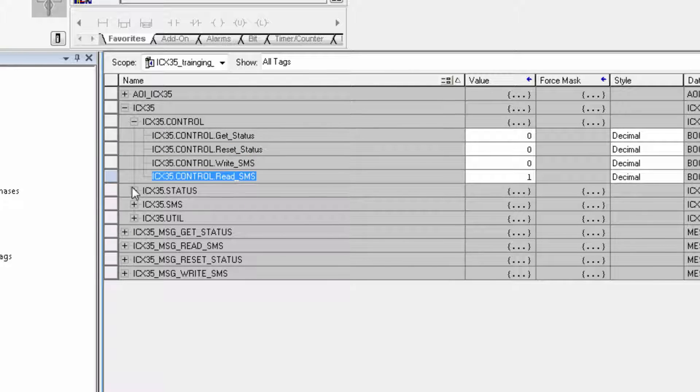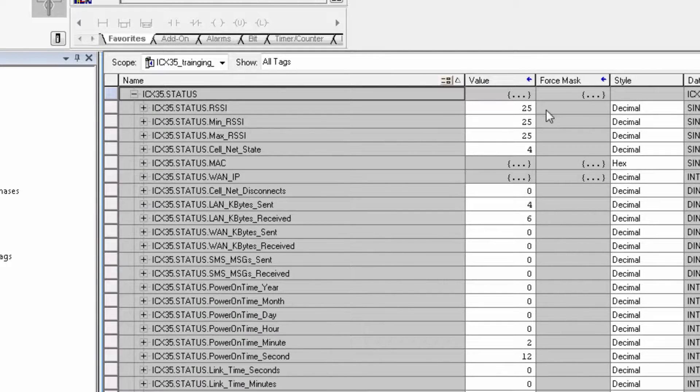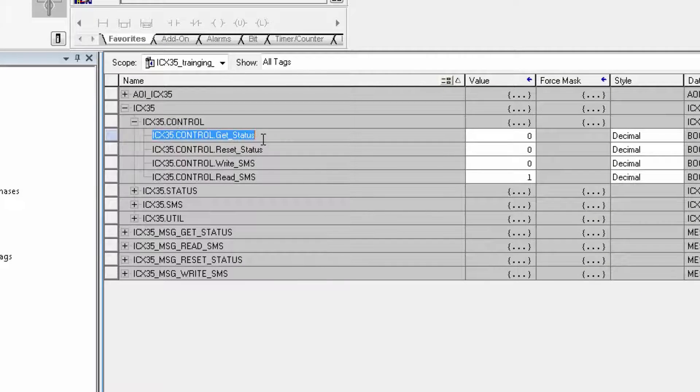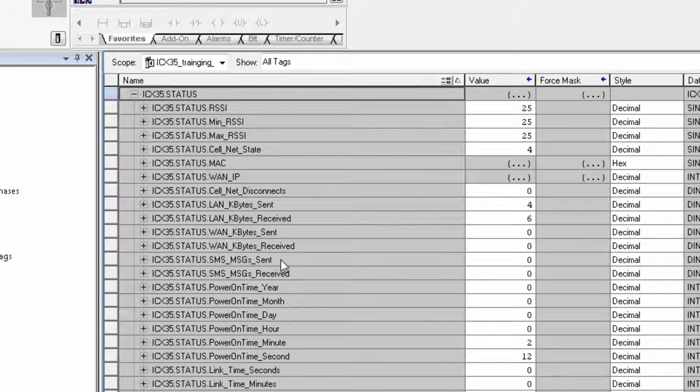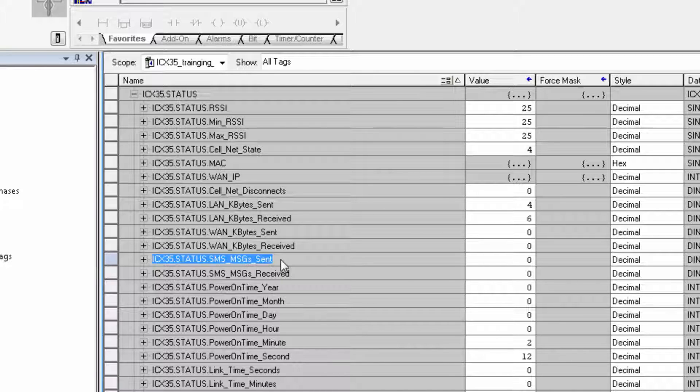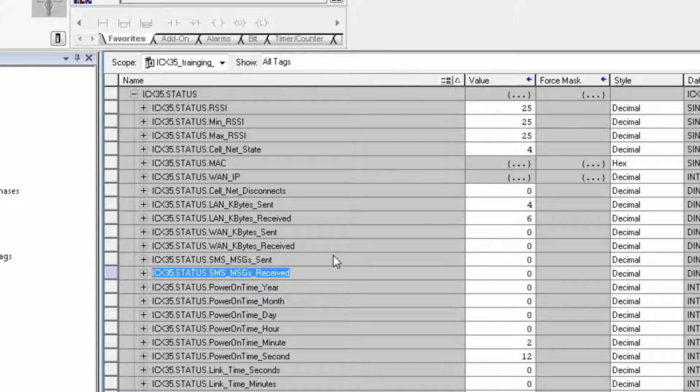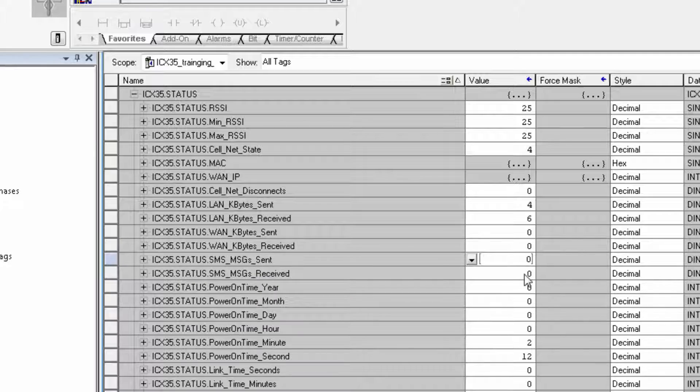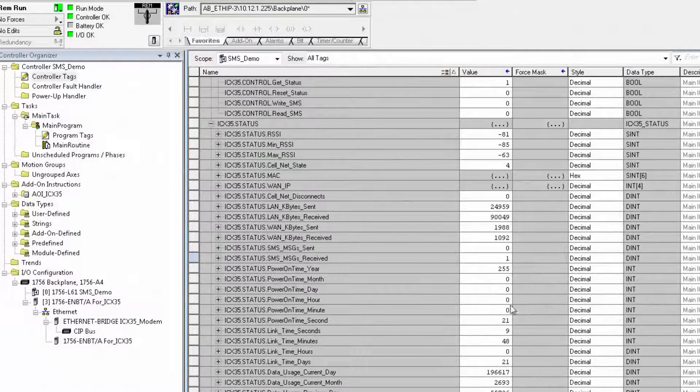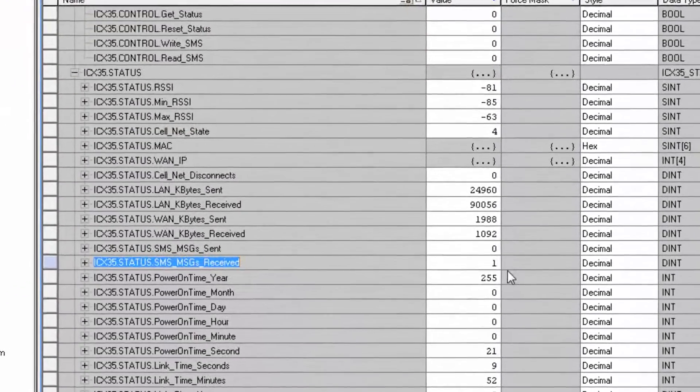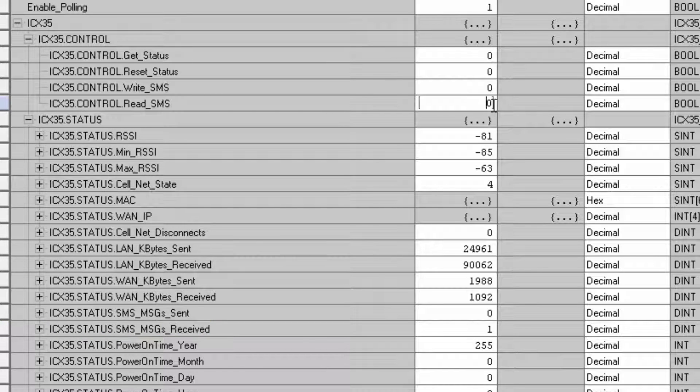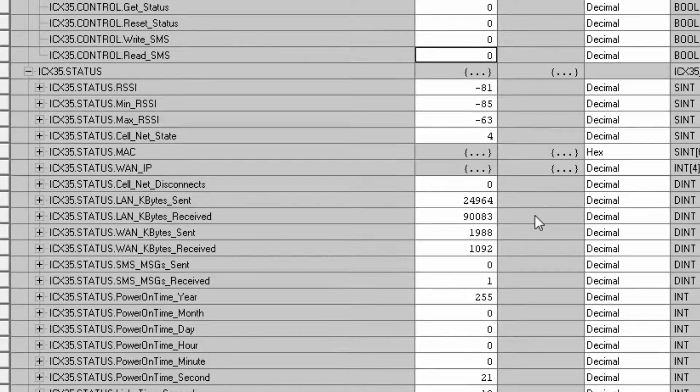We also have the ICX35 status tag. This tag will be populated once the get status trigger has been toggled by entering a one. Once you do that, the ICX35.status.sms messages sent controller tag should increment by one each time an SMS text message is sent successfully. You can check for received messages under the SMS messages received tag. These message counters are how the application knows that the ICX35 has sent or received a new SMS message. Once you have a program up and running, ladder logic can be used to monitor the messages received counter and when it detects a new SMS message to trigger an SMS read command to retrieve the SMS message from the ICX35.